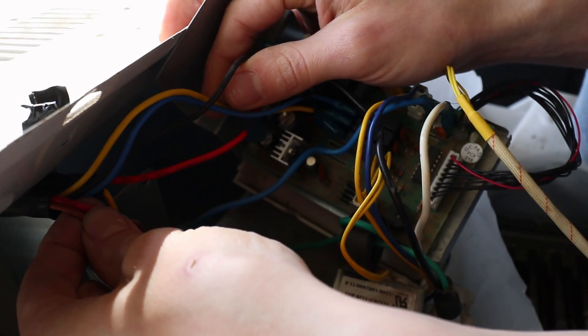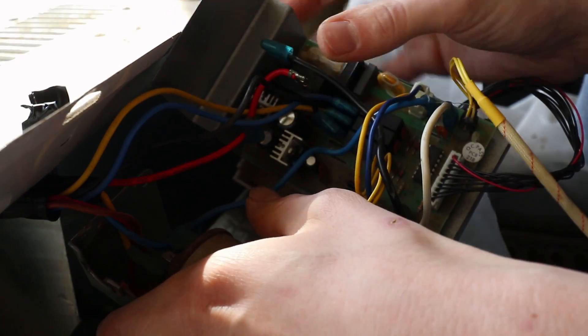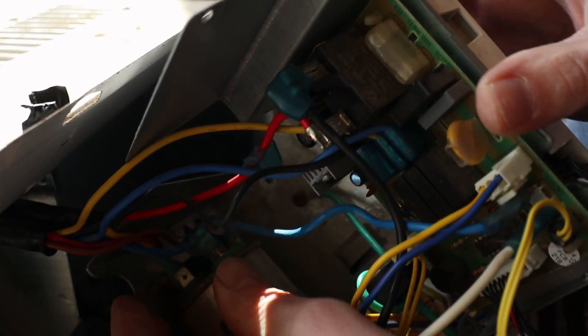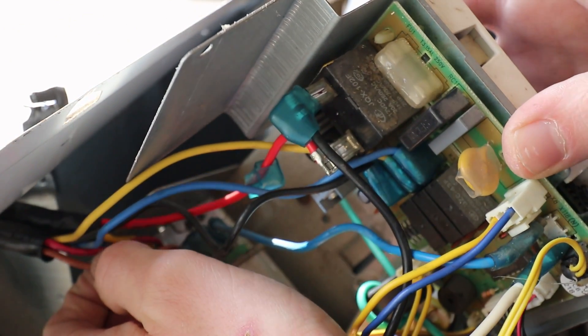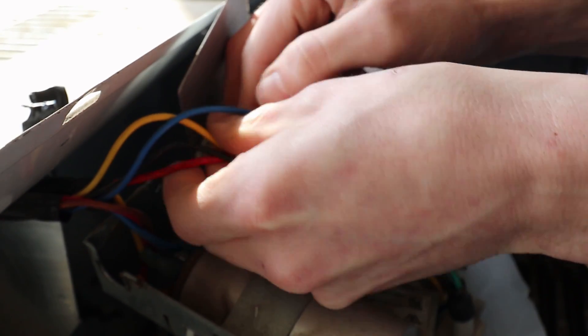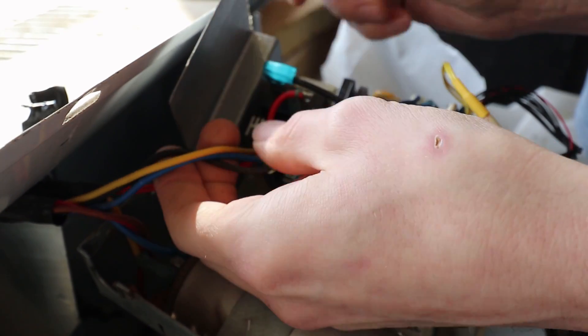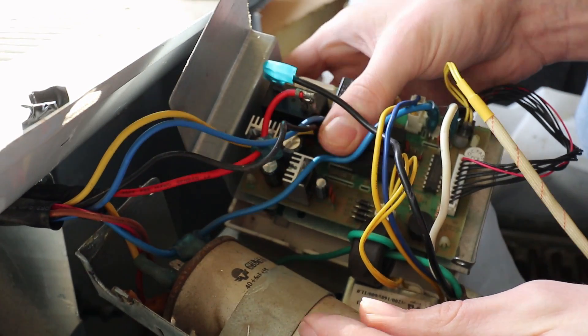You've got five wires and you're like, oh my goodness, why are there five wires? Well, this guy has three speeds on his fan. So we've got two wires going to the compressor, that brown and that pink. Then you've got three wires - the black, blue, and yellow are all coming down to the circuit board.